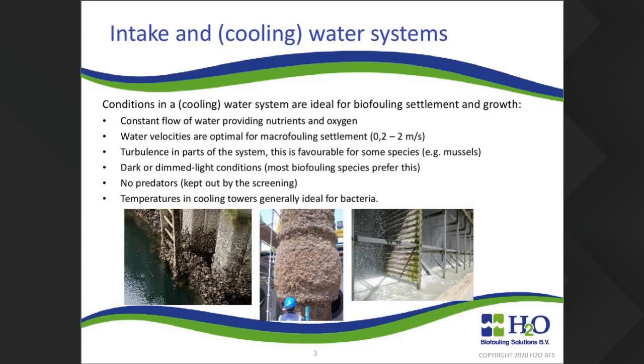The water velocities in a cooling water intake and cooling water system are generally between 0.2 and 2 meters per second. This is favorable for most of the biofouling species to settle and grow. There is turbulence in part of the systems, for example in bends, which is favorable for some species like mussels. They prefer these kinds of areas in a system. There is no light, or at least dimmed light, which is also preferable for most biofouling species to settle and grow.